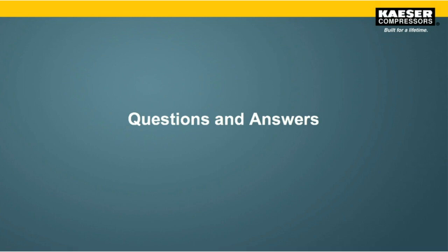Because we've talked a little bit about it here with the question and answer, but if you don't know how much air you're using, you should probably have an air audit done. A simple way to do that is just a load-unload cycle time. And like Grayson alluded to in the last question, look at it at different times of the day because you might be using more air right before lunch or right before shift change. So you can get an idea on a duty cycle just easily through that. And then you can figure out, okay, what do I need? And then look at the pressure profile as well.